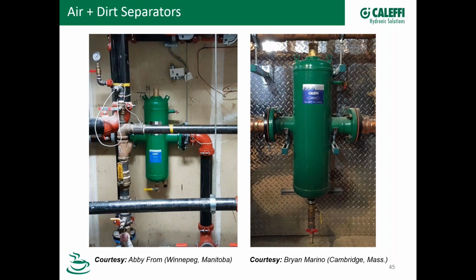If you've got a two-in-one device here, what's going to be the best bang for the buck on the particular application that you're putting it into? Because again, the temperature coming back to that system, if it's running a 15 or 20 degree delta T, isn't that much cooler than it is right at the outlet of the boiler. So that might help guide your decision. But we offer all the options: if you want to put an air separator on the hottest point, a dirt separator. Certainly with a magnetic device, I would encourage everybody to consider the magnetic device if you're using ECM technology, which I think Kevin's getting to next. That might be another determination on which device to use and also where to put it. Yeah.